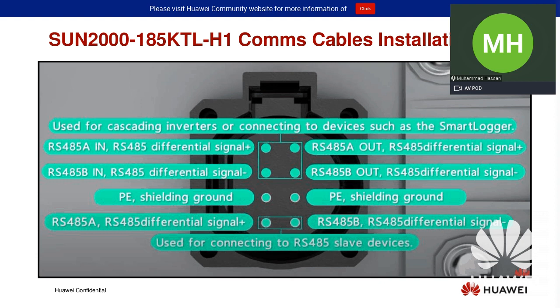Here, these are the new communication cable connectors inside that inverter. This is only applicable when you are using the RS485 communication cable with these inverters. These inverters also come with M-bus communication; they are capable of doing M-bus communication. For utility sites and large commercial and industrial sites, customers are using M-bus or PLC communication to communicate with that inverter.